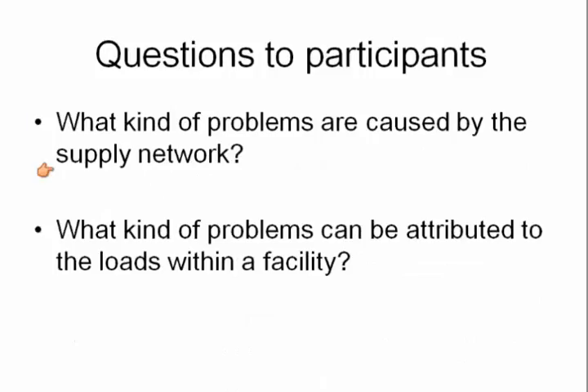So what kind of problems are usually caused by utilities? This is not industrial problems. What sort of issues do you generally see with what the utility supplies a factory or an industry? Some examples of problems. Brownout, yes. Voltage flicker, voltage sag, over voltage, transients.